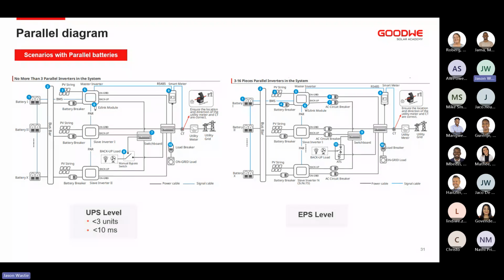The module you'll connect to whichever inverter you deem to be the master inverter, the rest of them automatically follow. You will need to remove all of our Wi-Fi kits, LAN kits, Wi-Fi LAN kits, 4G modules, any communication device that is connected to the other inverters, because the inverters will connect to each other using an RS485 cable, and all of the communication will be done with the EzLink module.